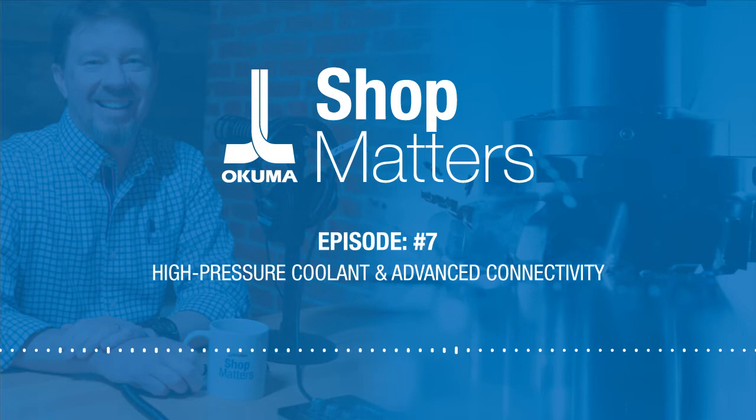A variable pressure is good from a standpoint of many customers use live driven tools, and some live tools are not capable of 1,000 PSI, so they may want to turn the pressure down, and our unit will do that automatically through the control. So if they need 300 PSI for a particular tool, they just change the parameter, and the unit automatically will slow down and still maintain full volume, but at that pressure.